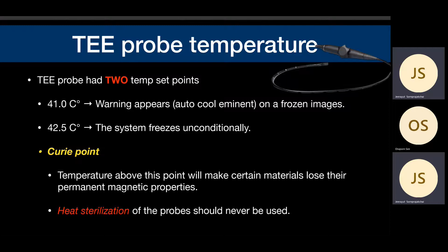But sometimes the doctor is too focused on doing the procedure, the patient moves around, or the patient won't cooperate, and the doctor is not looking at the technician. We are looking at all this, as I said, we work as a team. You monitor the vital signs, look at the patient, BP, and whatever is not good, you need to alarm the doctor. So if the temperature goes to 41 and the doctor doesn't say anything, they can still keep working. It will go up to 42.5, then the machine freezes, because it doesn't want the temperature to go up further. And then you get panic. So at least you know why the system freezes suddenly. If it freezes, you stop for a while, and when the temperature comes down, it will work again. So you make sure that no damage is done to the patient. Okay.